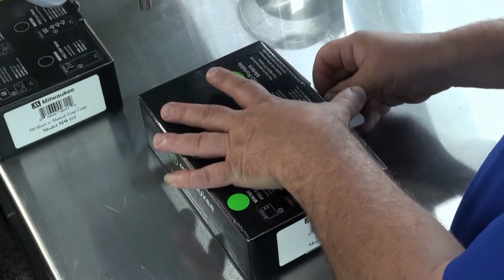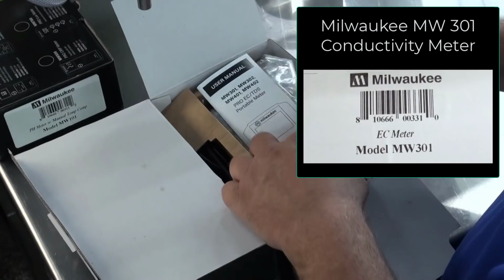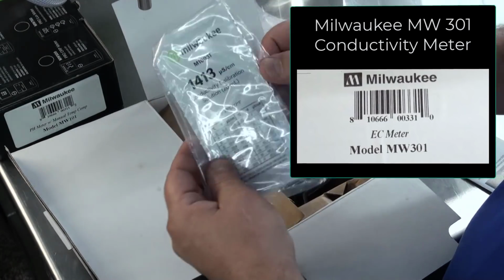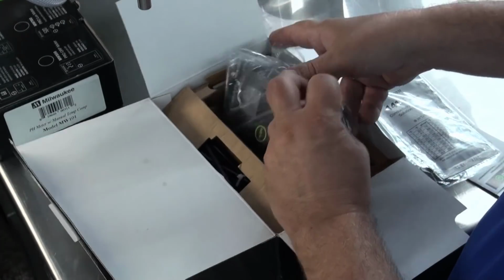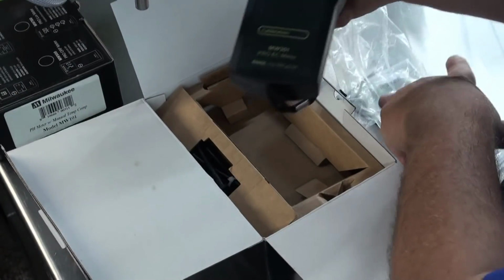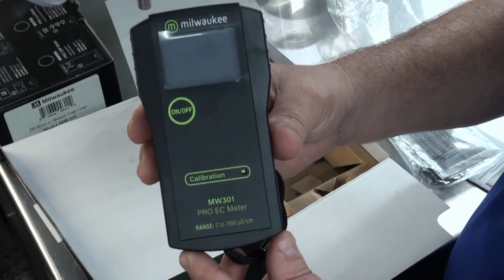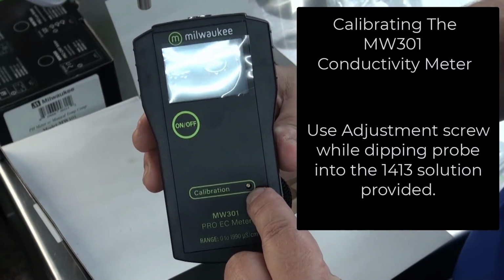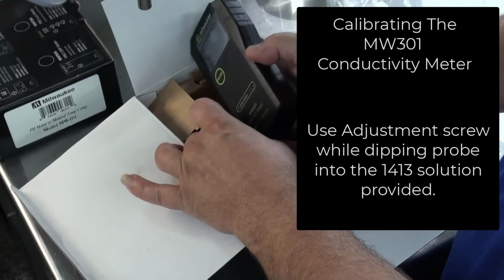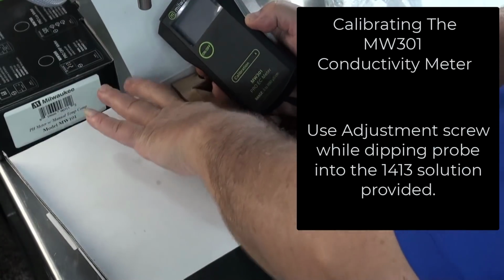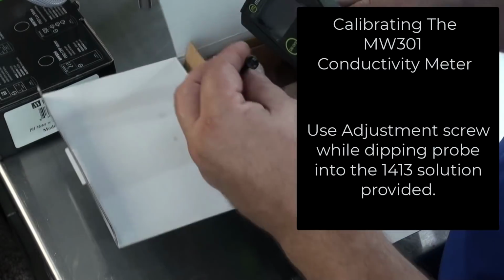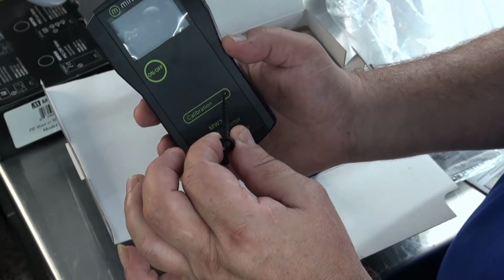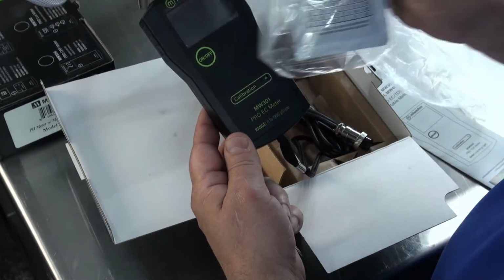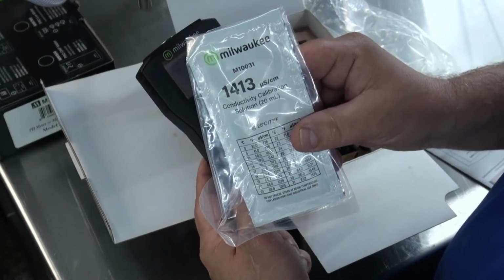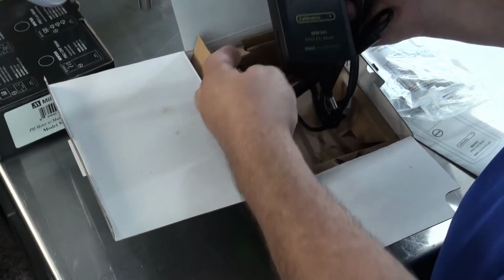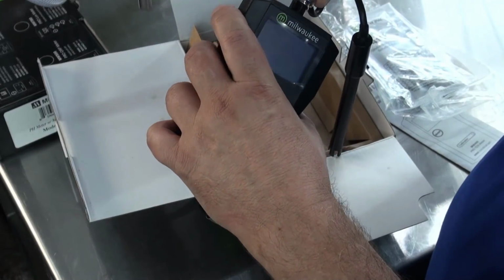Now we're going to unbox the MW301, which is your conductivity meter. The conductivity meter also comes with calibration solution. On this one, we're going to cut it short so we don't bore you to death, but if you look closely, you have the same calibration screw right here, and in here you've got the same little screwdriver. We already calibrated this, but this is how you would calibrate it inside the 1413 solution, which comes with the unit. What we're going to do here is hook up the probe.